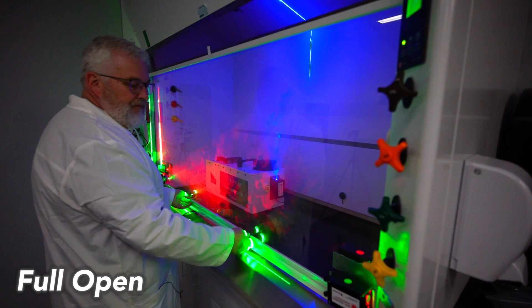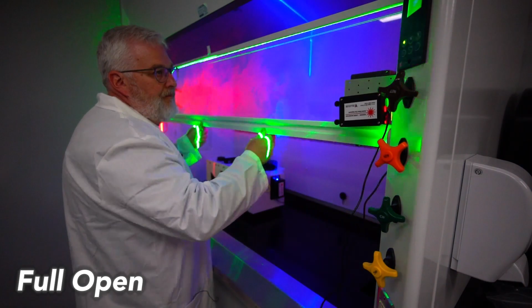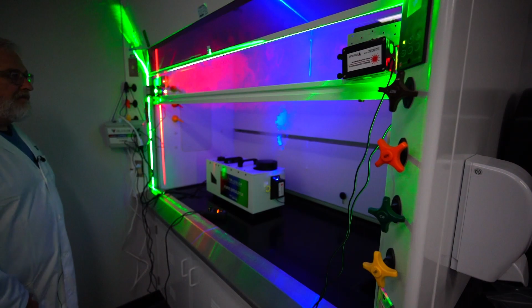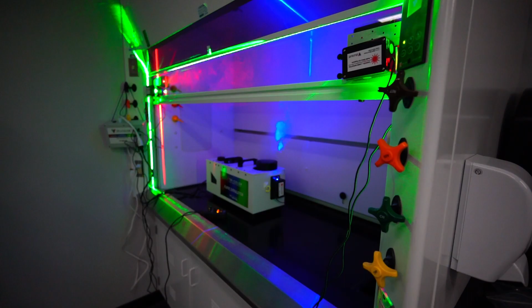But it's not really actionable information. And so really, to know if a hood's working, we need to measure dynamic containment in real world challenges. And that's what we do. The full open sash position is for setup only, but we want to see what the hood is doing in its worst sash position. So raise the sash to full open and just stand back and observe and see what's going on. Notice the red smoke behind the sash at the top of the hood. See what it's doing and see if you can find any green flares of loss of containment.